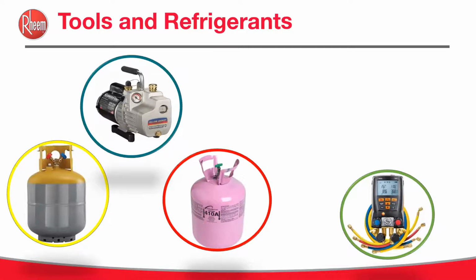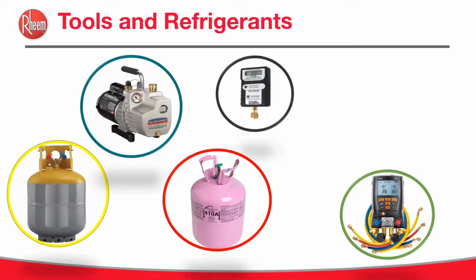Properly maintained vacuum pump, like I said, we also need a micron gauge. Micron gauge is to verify the system is properly evacuated. For the best reading on the system, the micron gauge should be located at the furthest point from the vacuum pump. And did you know at sea level, you have 760,000 microns. So you have to have a micron gauge. You cannot do it with the gauges alone.